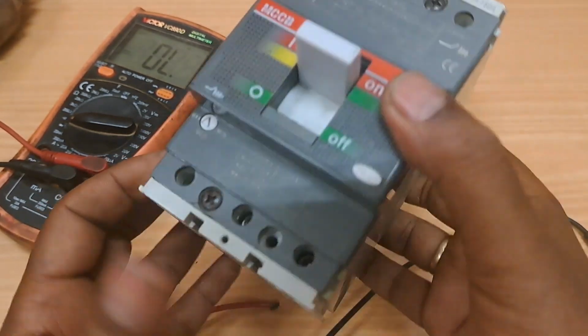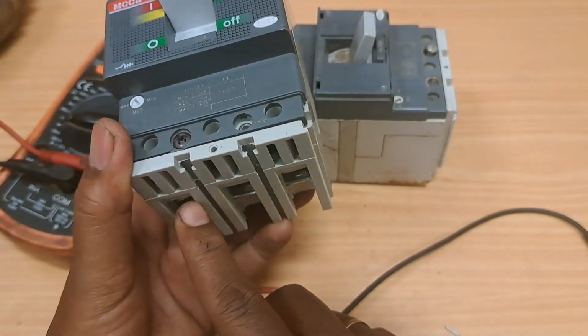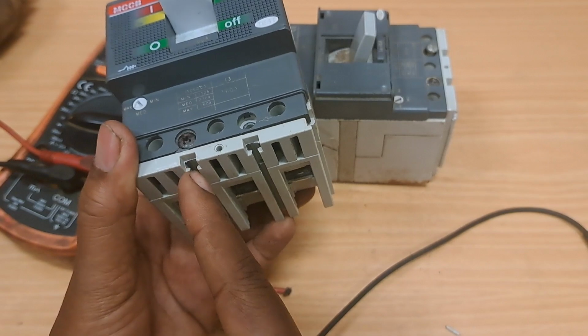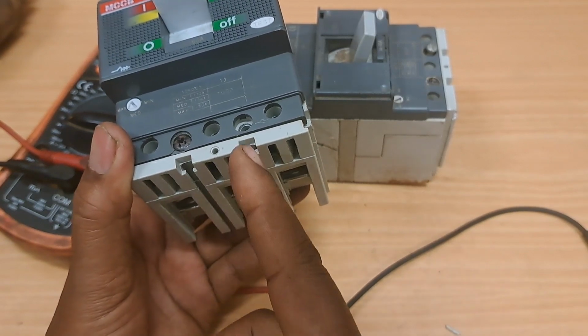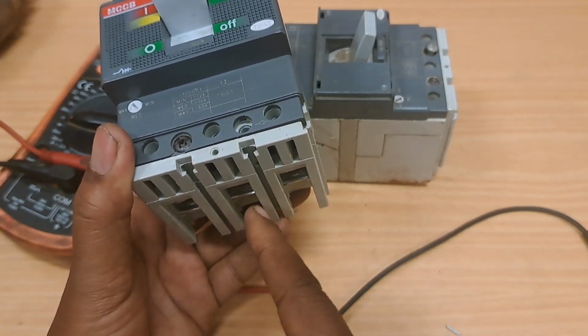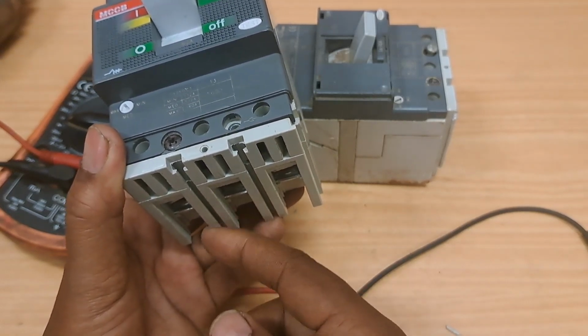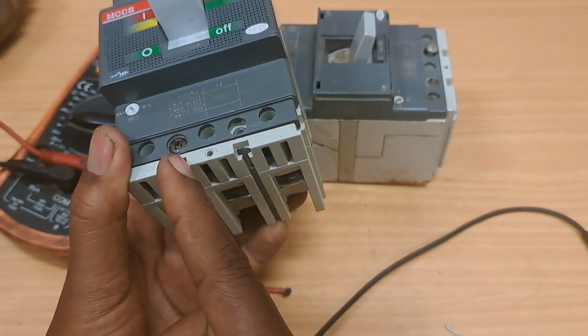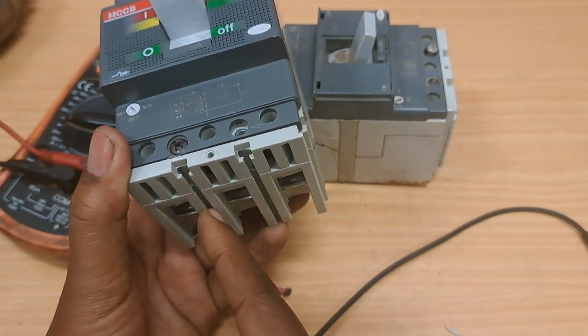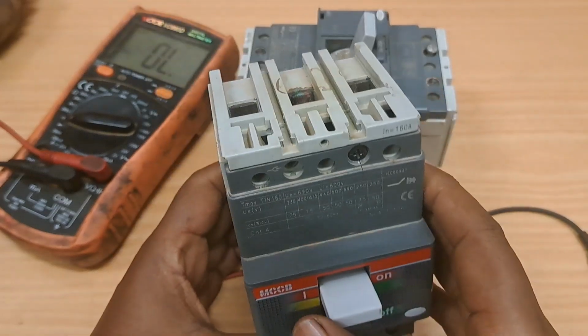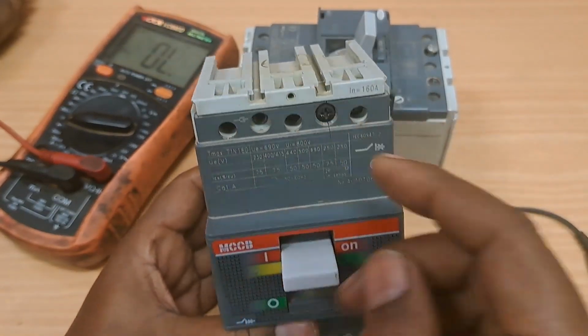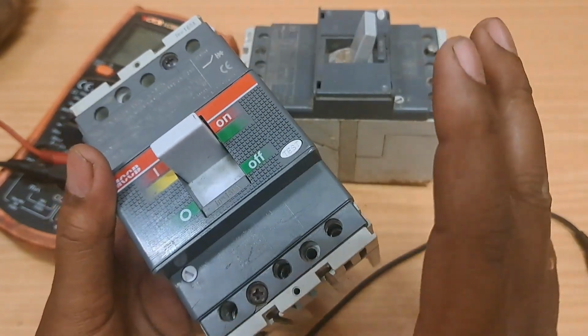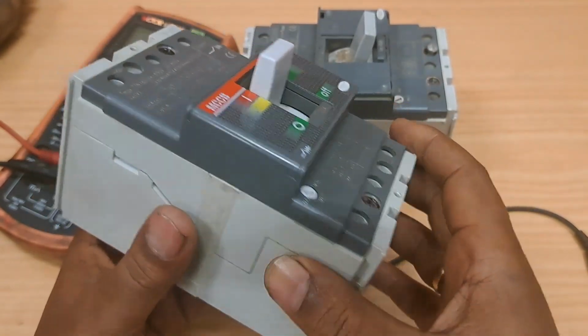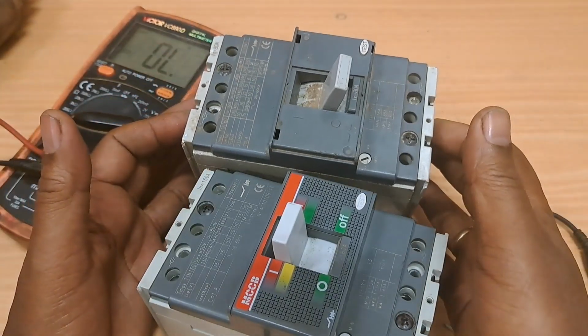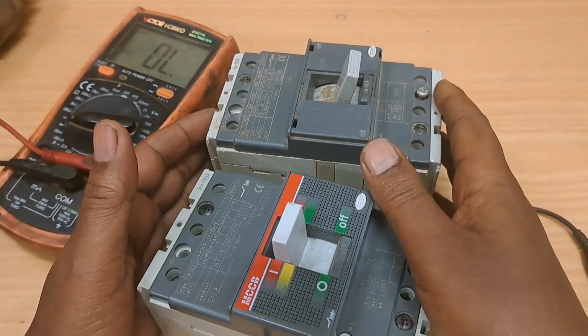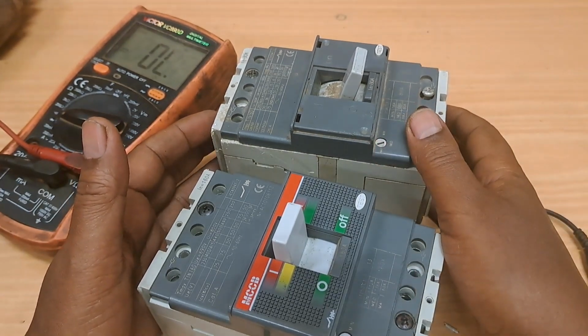When you are connecting this, always remember to insert separators right here. This slot is for inserting separators that can prevent any type of cross arcing, or if there are any bare metals that can cross, that can be prevented by inserting insulators in here. So make sure that you insert them on both the outlet and the inlet direction as well. So this circuit breaker is defective, it needs to be replaced, but this one is working nicely, so it can be reused again. So this is how you can simply test circuit breakers.